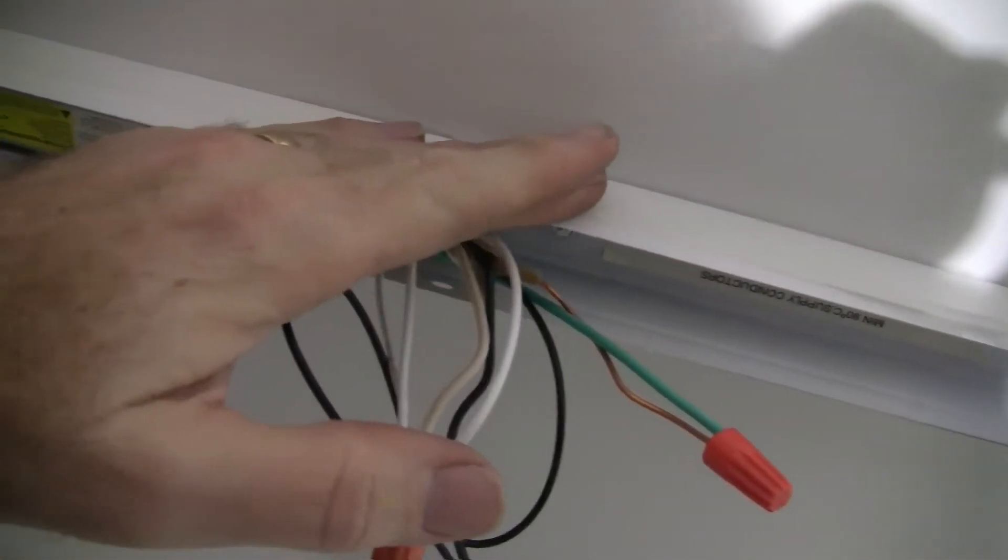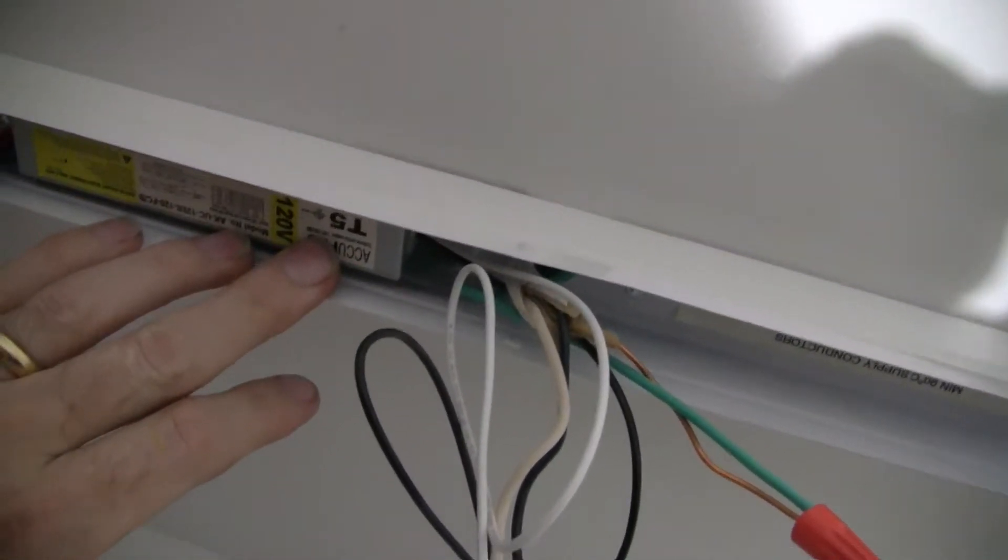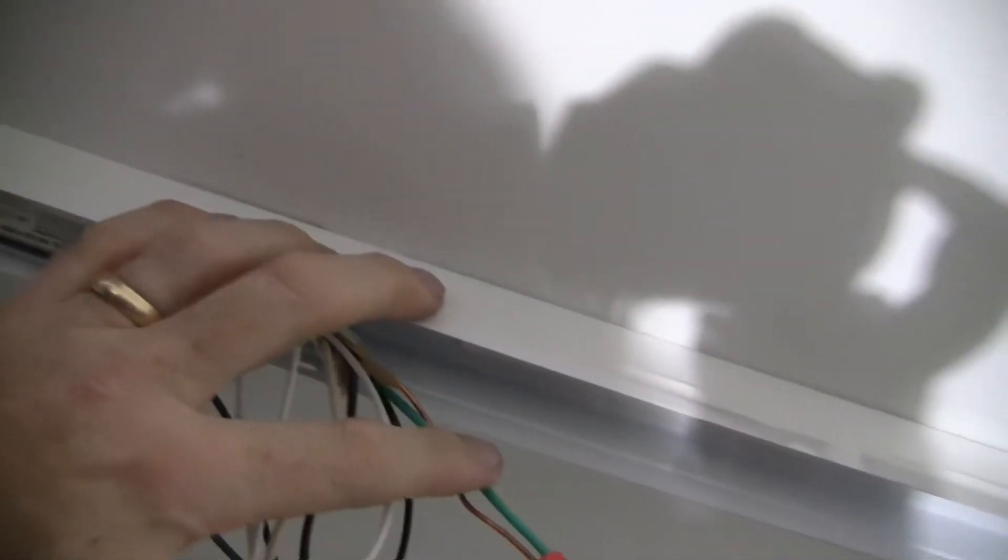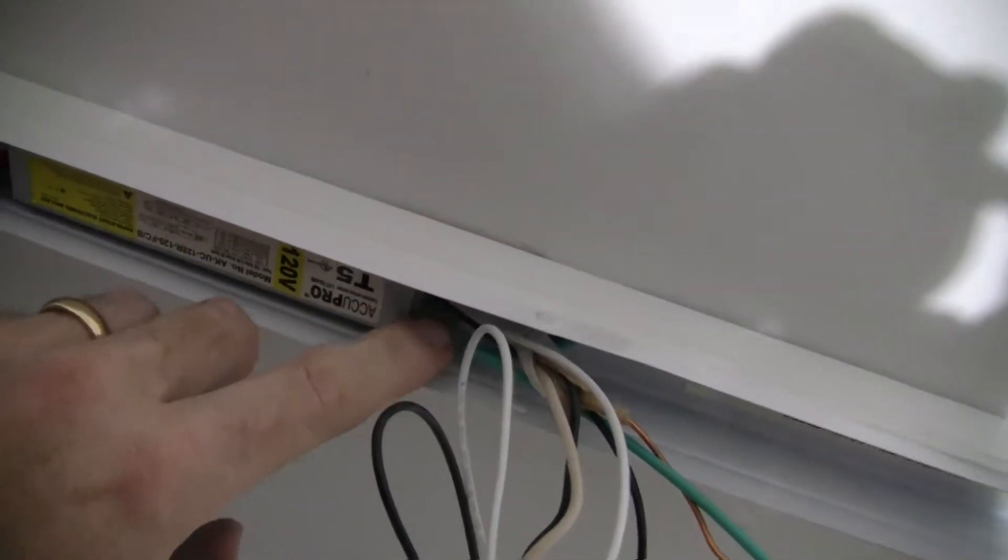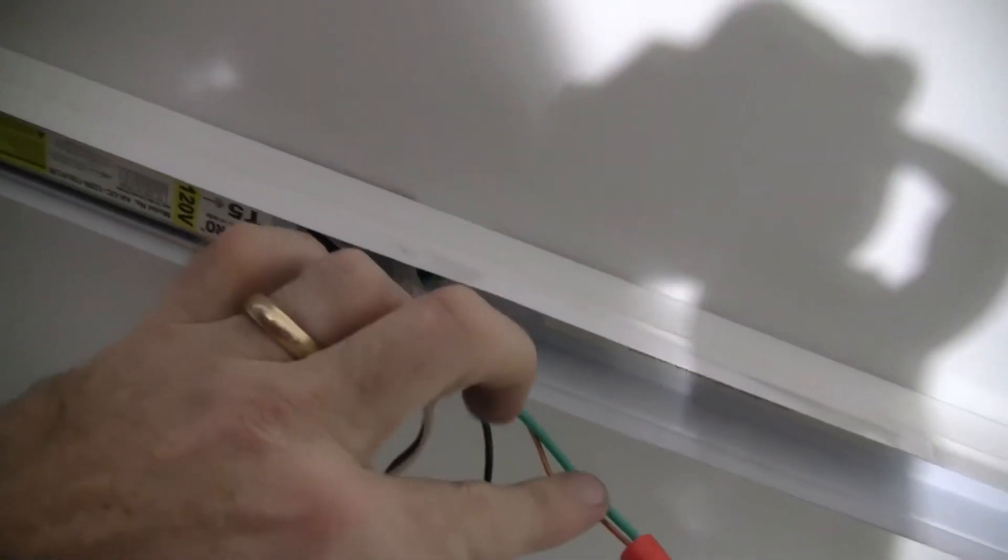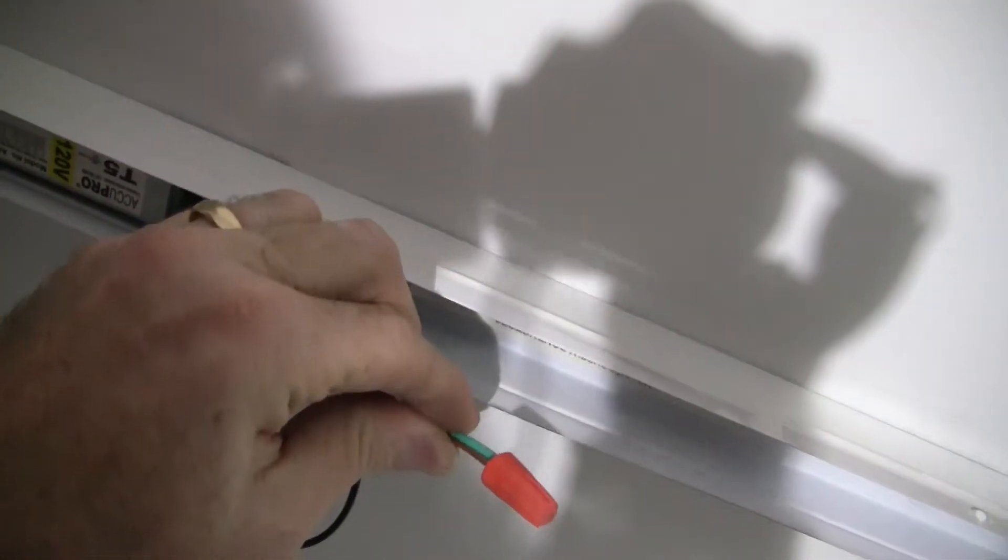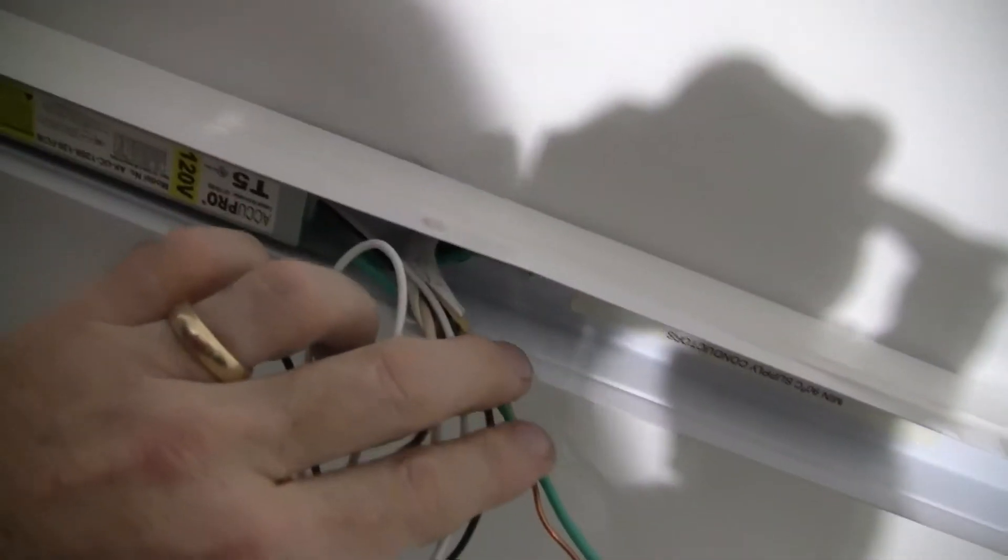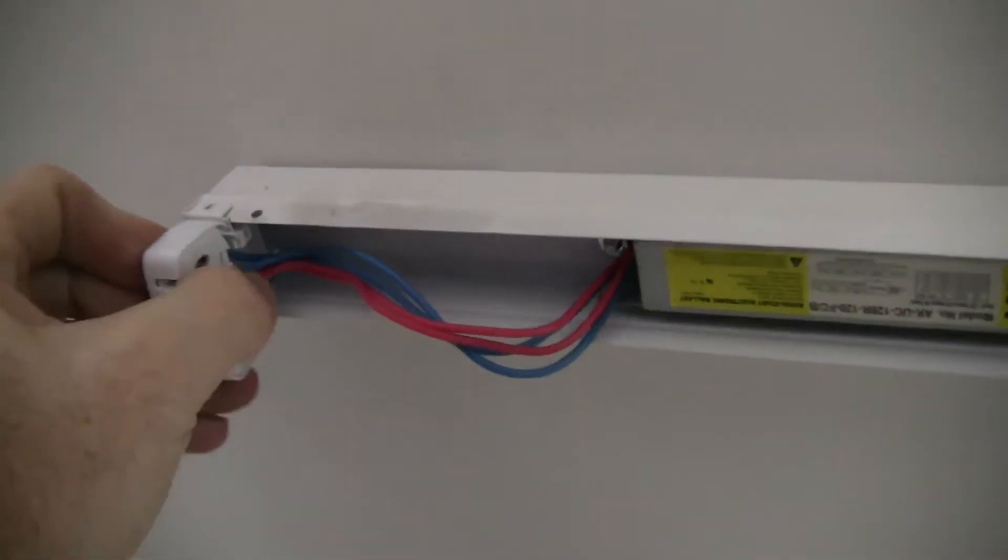Ground on this one is grounded straight into the light fixture. A lot of them are that way because once you tie this in, the ballast grounds to the fixture and then the fixture grounds to ground. Some of the bigger ballasts, you may have an extra ground wire that comes out of the ballast. Be sure you hook that in with your ground. Bare wire on your house wire is ground. Usually green is always ground and there's usually a green screw, green coated screw that you hook into. Alright, so that's all the basics of it.